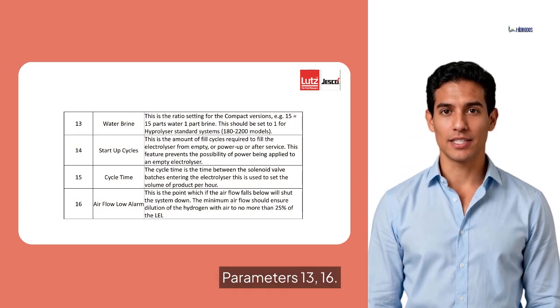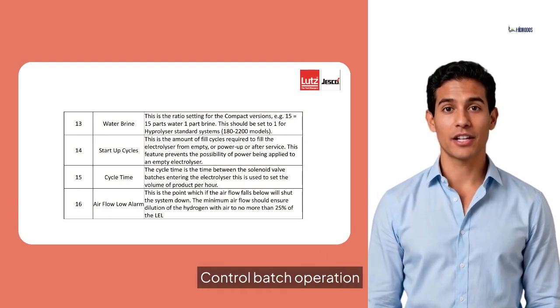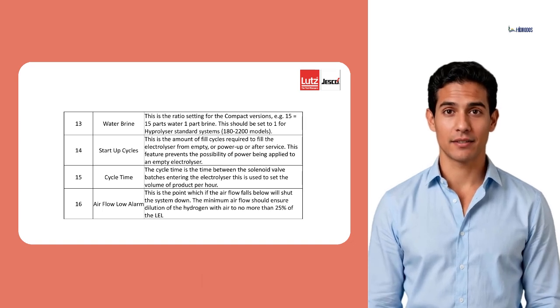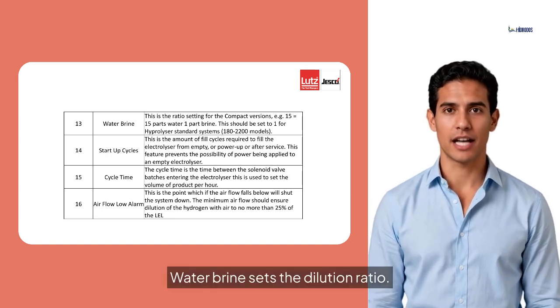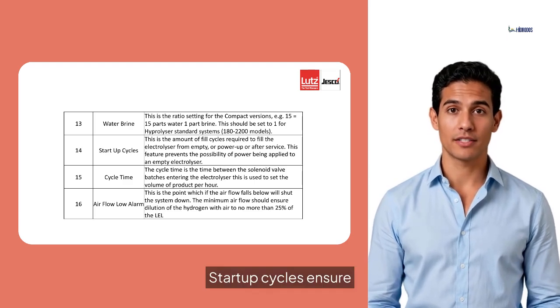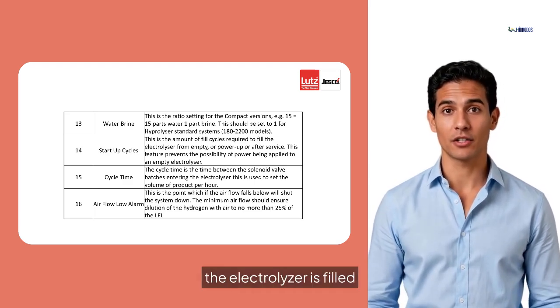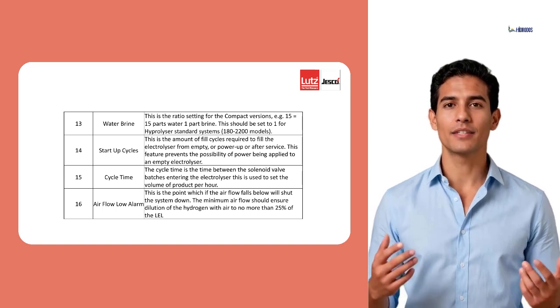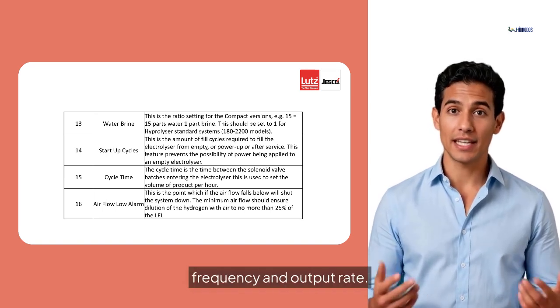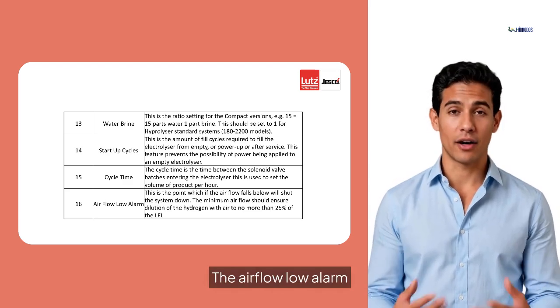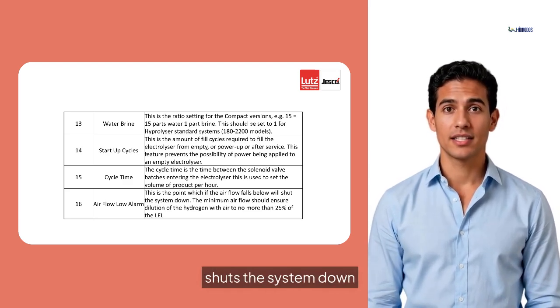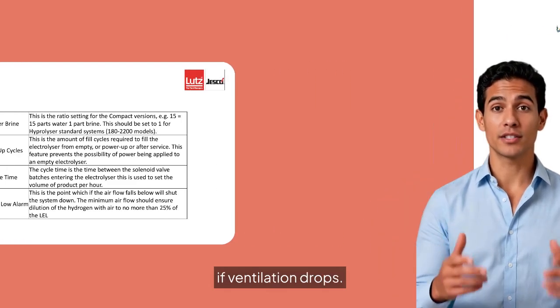Parameters 13 to 16 control batch operation and ventilation safety. Water brine sets the dilution ratio. Startup cycles ensure the electrolyzer is filled before power is applied. Cycle time determines batch frequency and output rate. The airflow low alarm shuts the system down if ventilation drops.